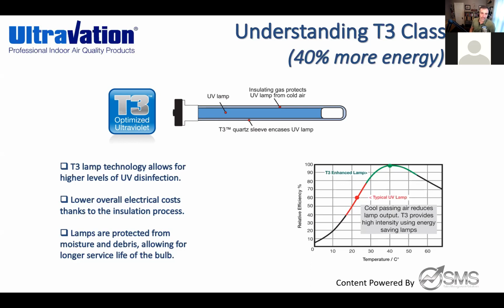The advantage of this design is that, per the graph here, a standard UVC lamp, entry-level lamp, is only going to peak out between 40 to maybe 75% efficiency because of temperature fluctuations, moisture, and possible dirt and particulates. Once you use a T3 class lamp, you're protected from all that. You're going to be able to hit that 100% capacity coming off the lamp.